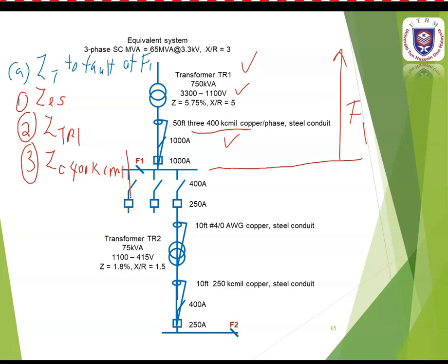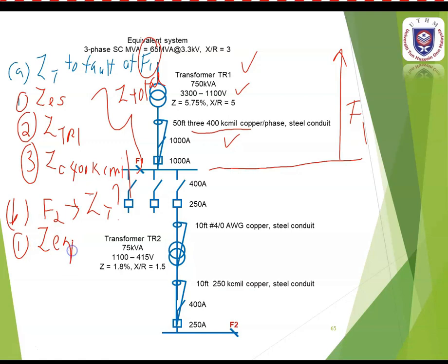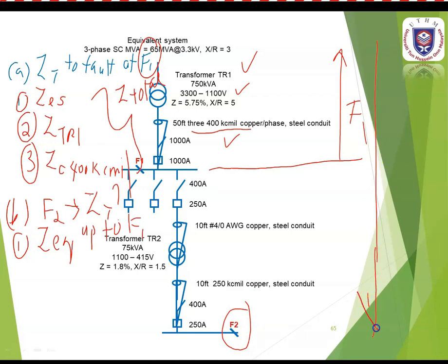The equivalent system impedance for transformer TR1 is referred to the low voltage side. To find resistance and reactance referred to the low side, use: R_reflected = R_system times (Vs/Vp)². Then identify the percentage resistance and reactance of transformer TR1. Using theta = arctan(X/R) = 78.69 degrees, percentage R = %Z times cos(theta) and percentage X = %Z times sin(theta).